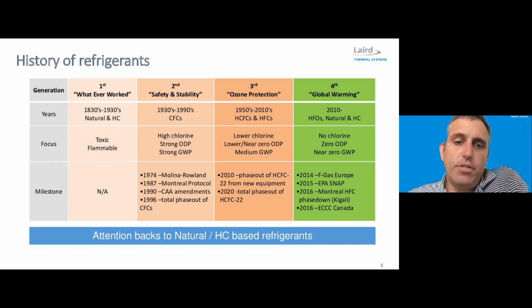And you can see some of the milestones that started taking place in the late 20th century that brought about some of the change associated with the third generation. So this was more aimed at reducing impacts on the ozone. And so this was a switch to hydrochlorofluorocarbons and hydrofluorocarbons. These had significantly lower amounts of chlorine, and some of the refrigerants had absolutely none, that had no impact on the ozone depleting potential. But at the same time, these still had a high GWP, or higher GWP than what we're really trying to go today. And this is what is happening in the fourth generation, or what we call the global warming sensitive generation.